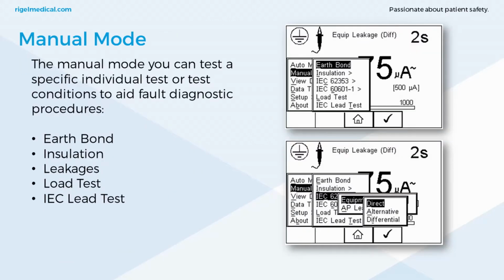Okay, so manual mode, you can test to a specific individual test or test conditions to aid fault diagnostic procedures. So you might want to carry out individual tests, very easy to do. You just go to manual mode in the menu and select either earth bond tests, insulation tests, your leakages, load tests, and IEC lead tests. And in this example, the IEC 62353 and 60601, you'll note that on the safety analyzer we're using today has ASNZS 3551 configuration. So it depends on your firmware. You can have any standard installed on the 288 Plus.